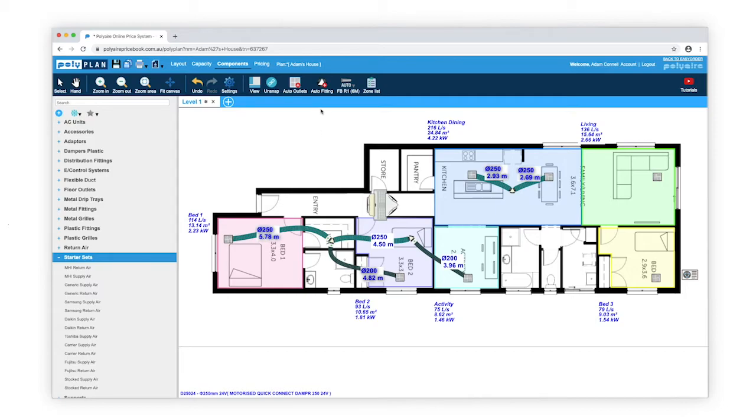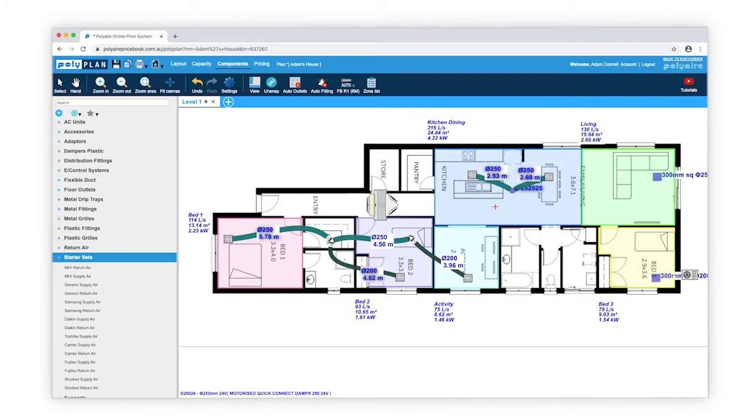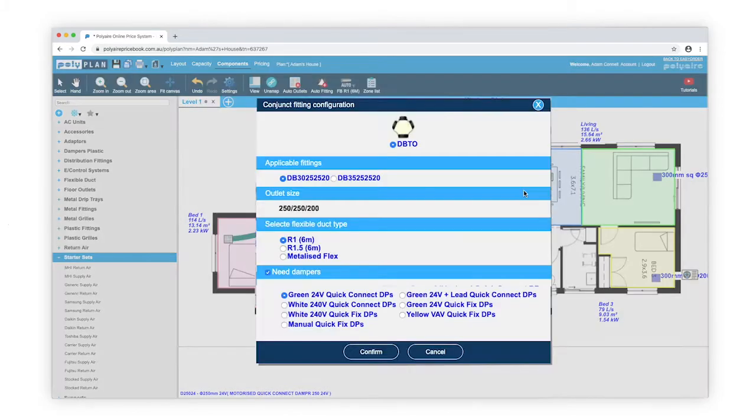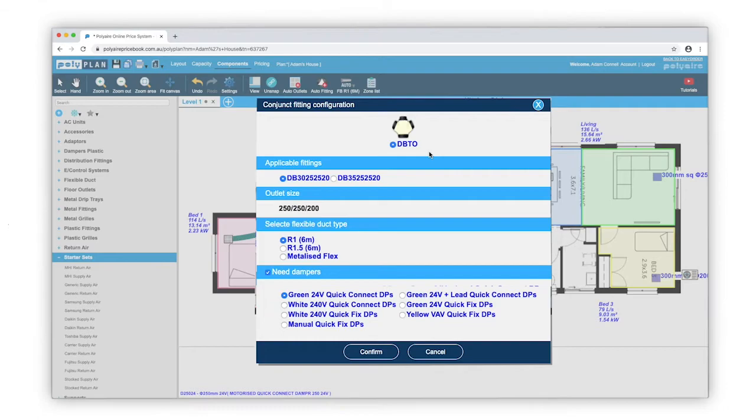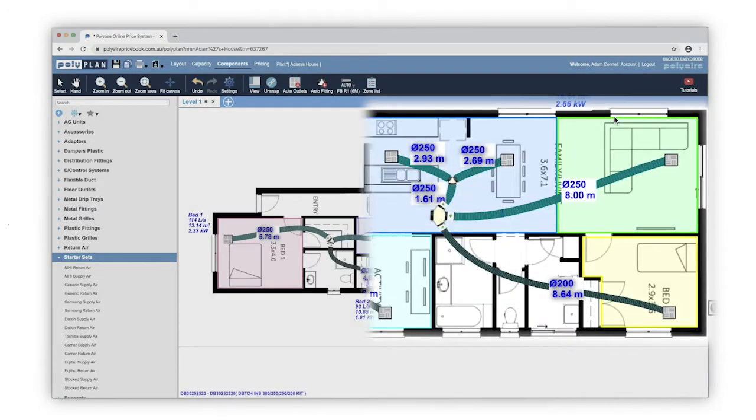The Auto Fittings tool can also be used to link up multiple fittings. Here, I'm selecting two outlets that need to be zoned, and my original Y fitting. Based on the requirements, Polyplan recommends a double branch takeoff, and because I selected Need Dampers, it has been zoned.